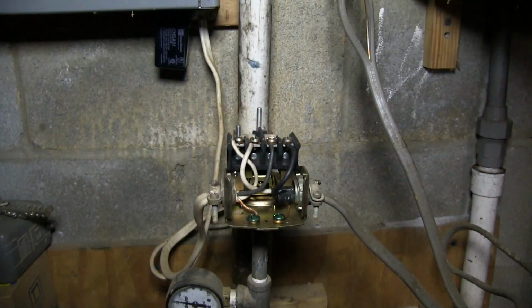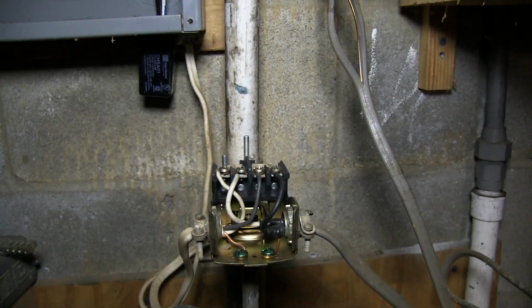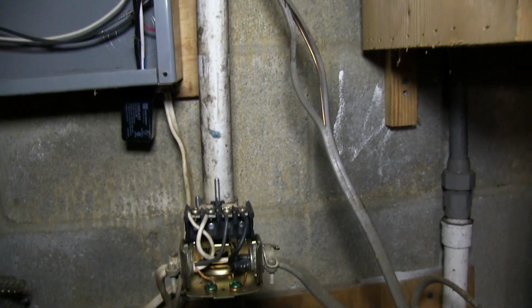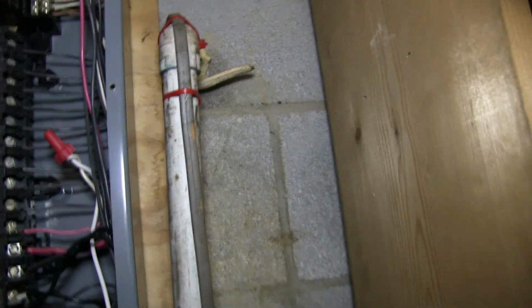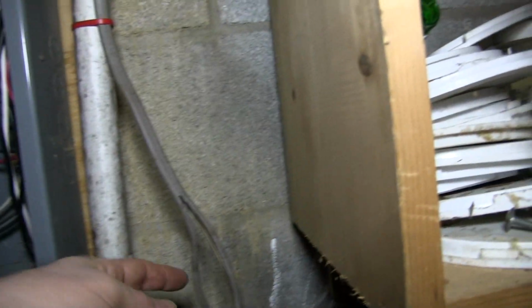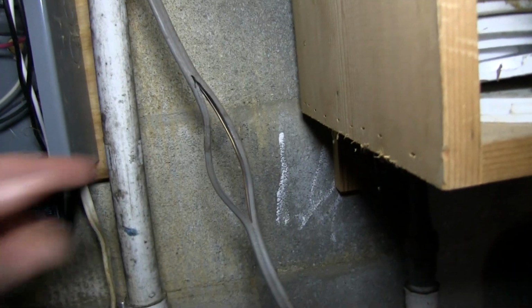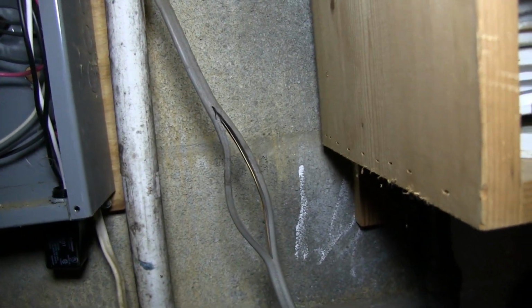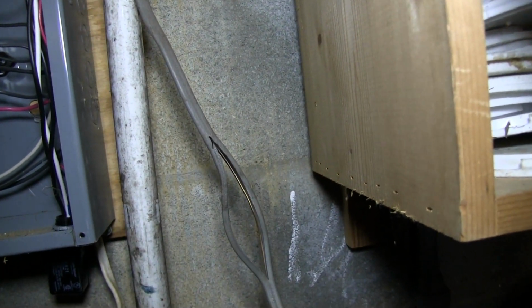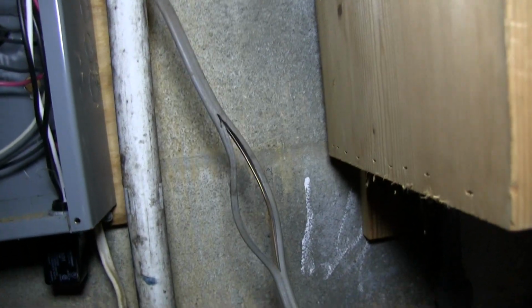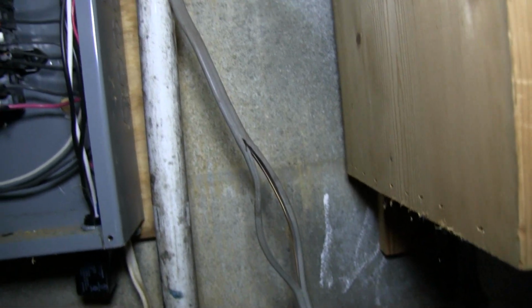Let's go inside. Alright, so here is the pressure switch. I've taken that apart so you can see it, and the wire coming in from the outside. This wire is split so we can put an amp meter on there, to tell when half of the windings are burned up, or if it's burned up altogether.